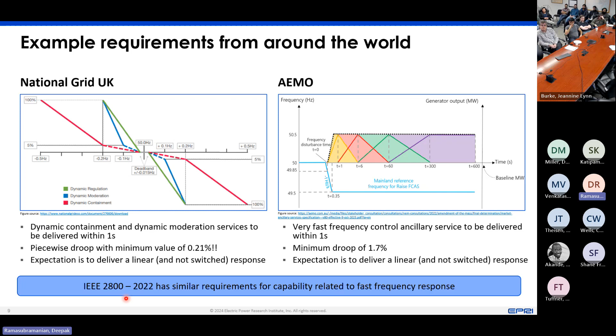We spoke about how an inverter-based resource plant has many inverters in the plant. You have many turbines, many individual inverters, and then you have a plant level control or a coordinator that is really coordinating across these different inverters in the plant. Now, if you apply all the voltage control only at the plant level, and you dispatch active and reactive power commands to each individual inverter, then when you have a step change of voltage, you would find that the response is a little bit sluggish, a little bit slow, delivered over multiple seconds. And sometimes there can even be a non-minimum phase response where the response goes in the opposite direction. Now, this is because there is communication delay.